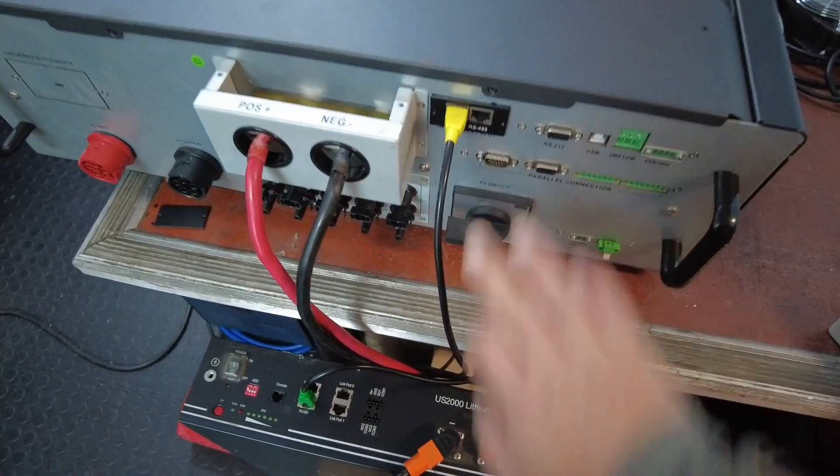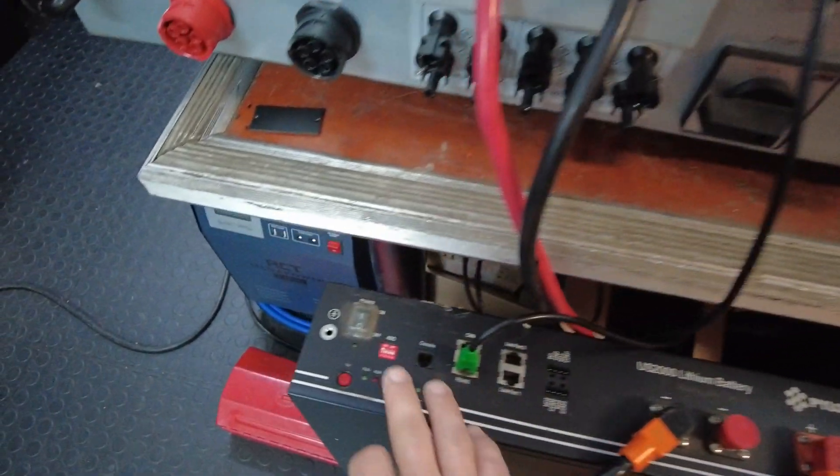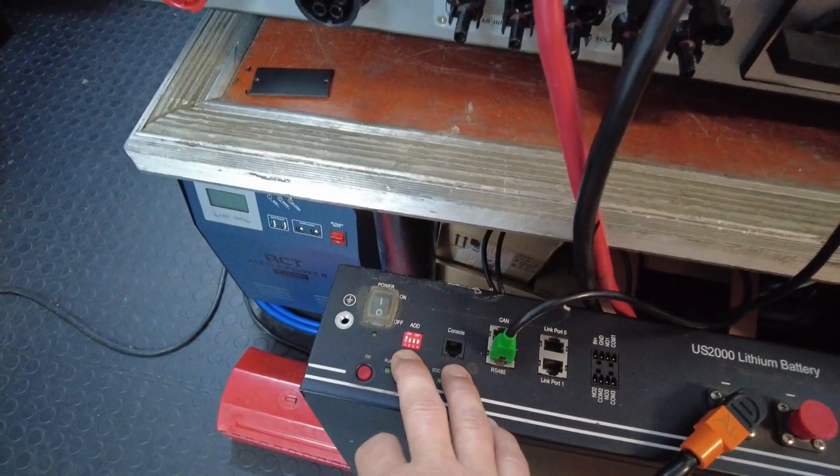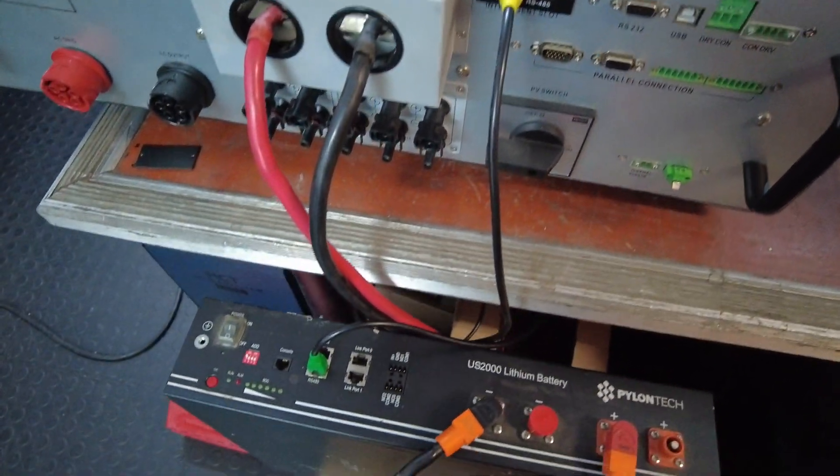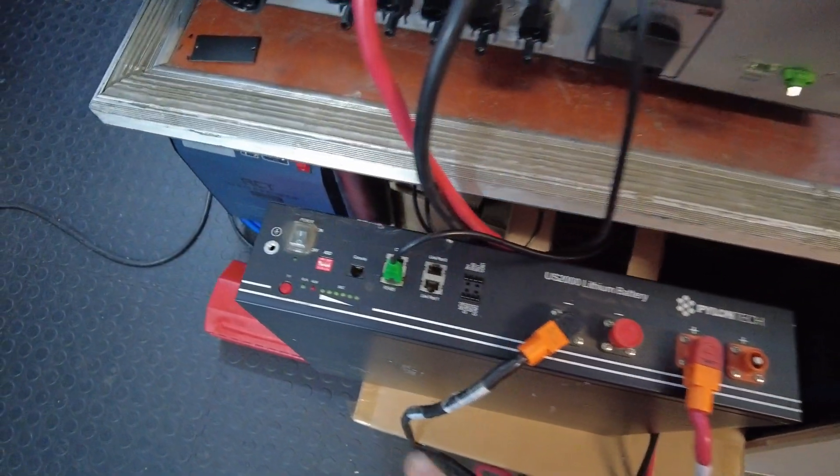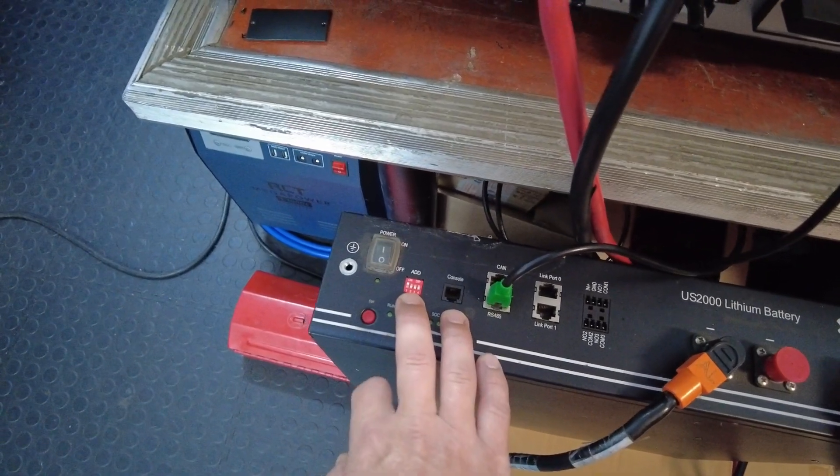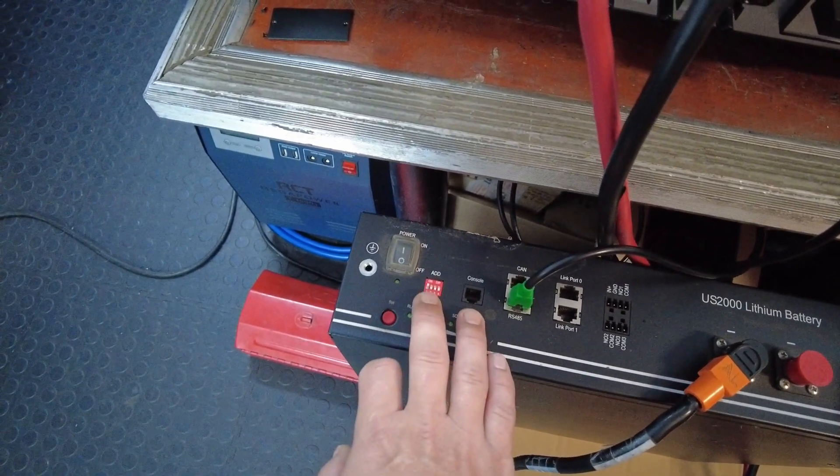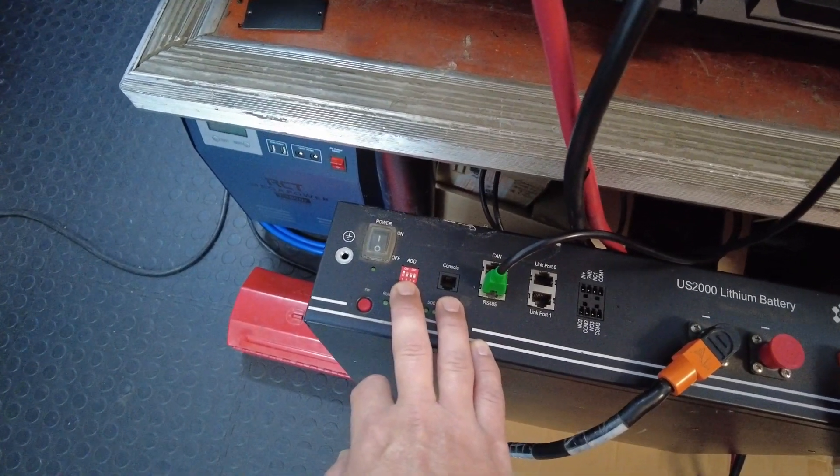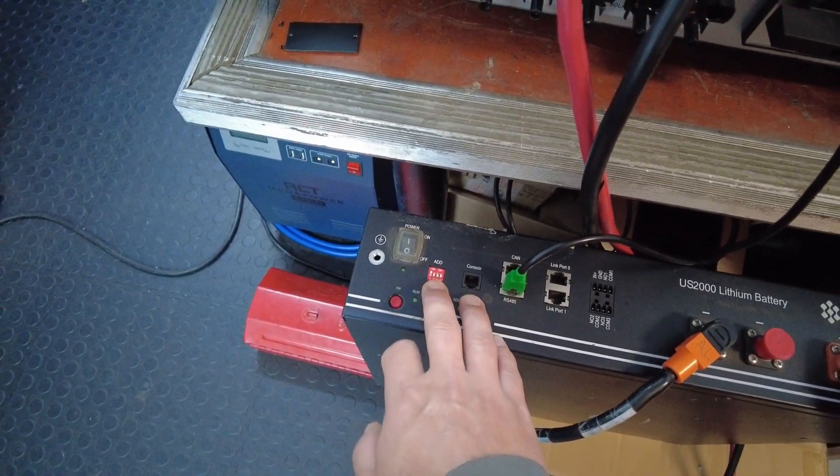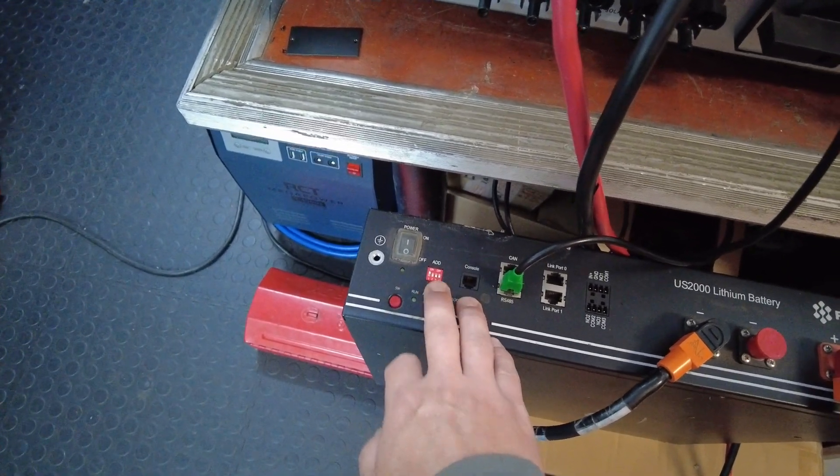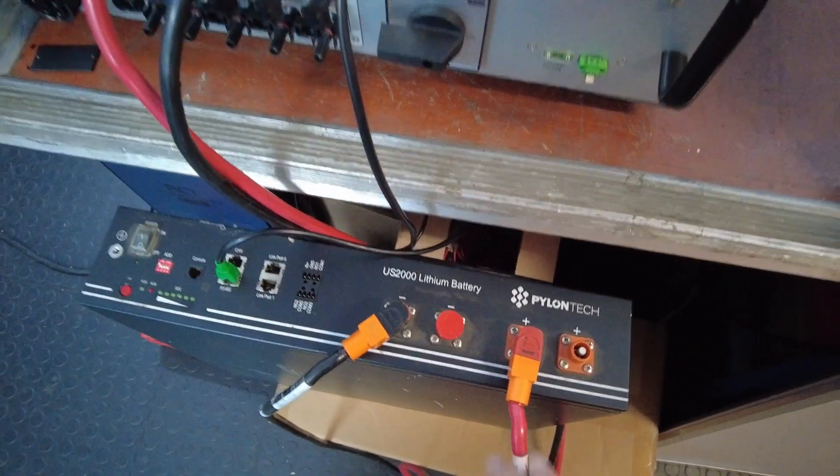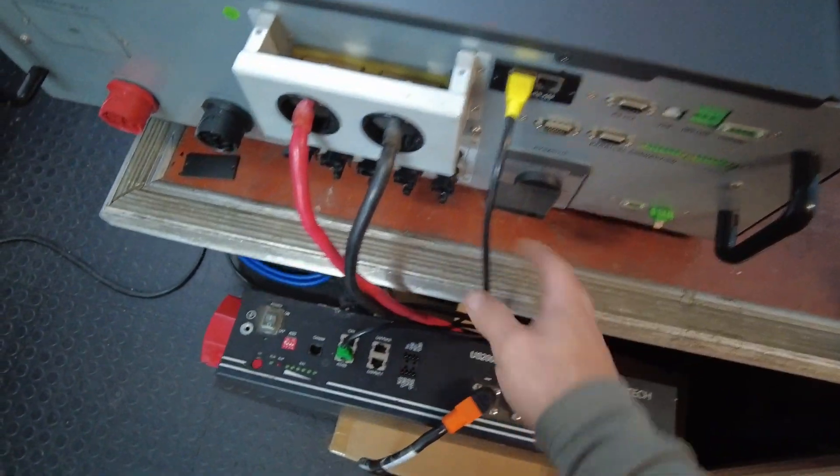Everything is currently off. Note that you can only make these dip settings while the battery is in the off position. It will not take any effect if you change these dip settings while the battery is on. Before we switch on, dip settings are set correctly, the DC cables are connected, Modbus card is inserted and the cable is connected. We can switch on.